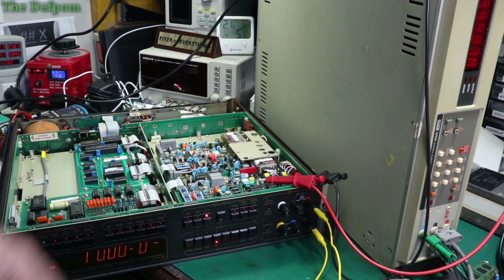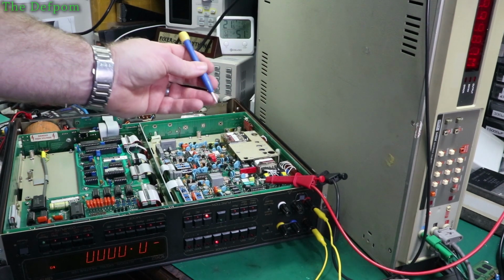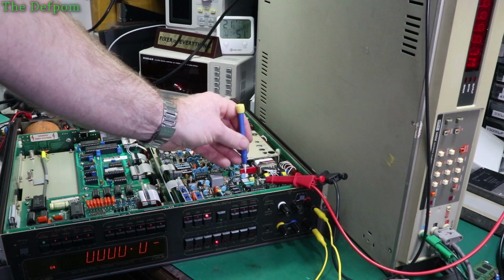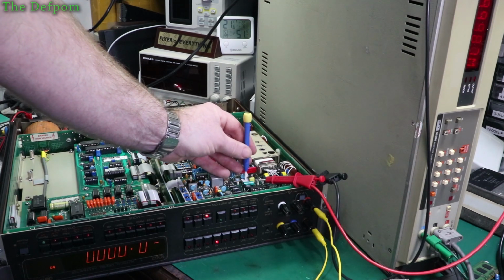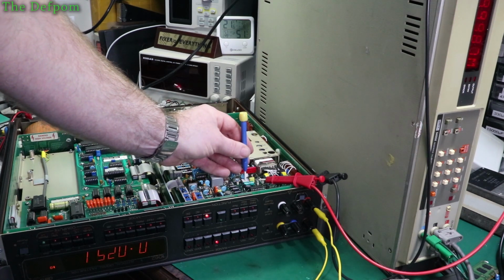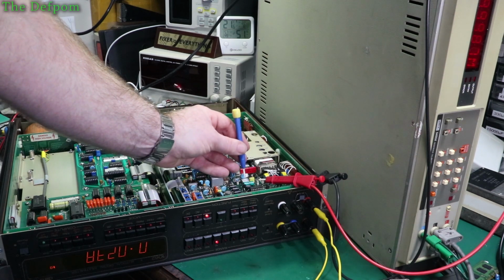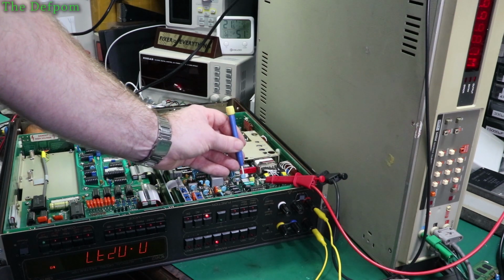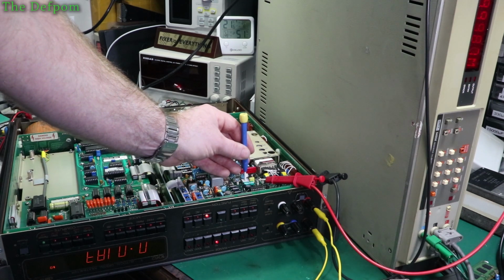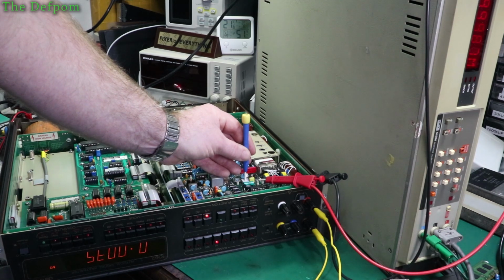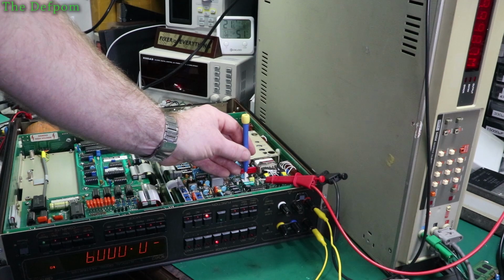I've already done a bit of a tweak on this. I'm getting pretty close. It has to be 0 plus or minus 300 microvolts on the bias. This is a DC bias, and it was adjusted about here when I got it, I think. Yeah, about there, which is 2.4 millivolts, which is way off. So if I bring it back down to about where it should be, I should be able to get it that close, and I should be able to get it basically 0. It's only drifting very slightly with noise. I'll show you in a second once I get it set.